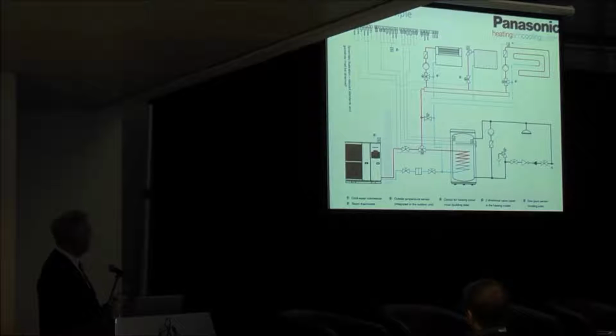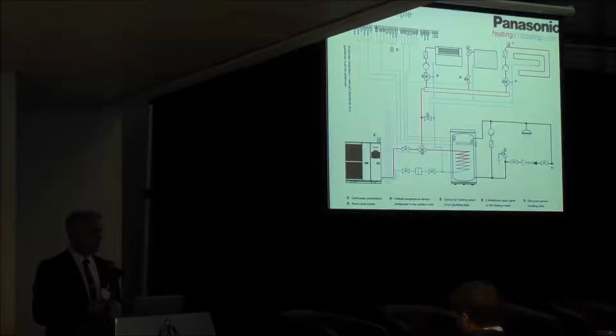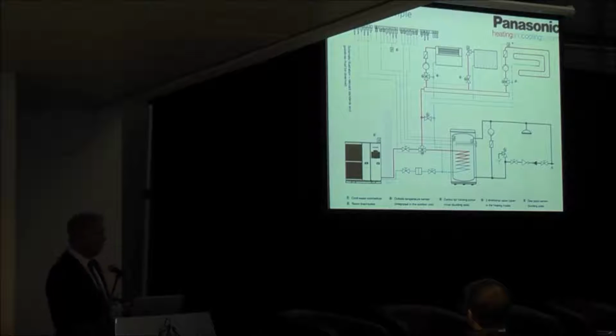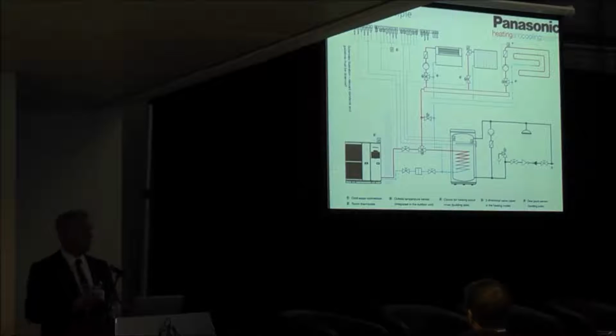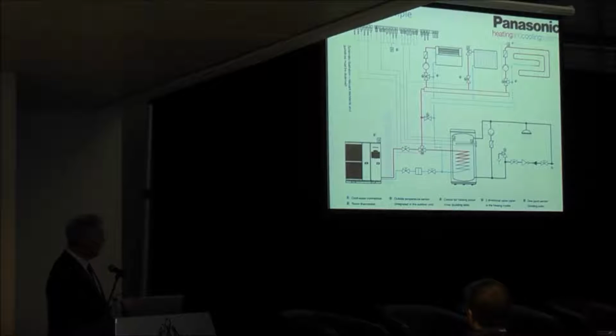Okay, friends. We size the heat pump for the biggest load, be it the heating in the house or the hot water. In a passive house, the biggest load is probably going to be your hot water demand. But the heat pump is sized to do your biggest load, one or the other. It's not sized for both. So we have a flow and return coming into the house. We're feeding the domestic hot water cylinder first. So when we commission the heat pump, the first thing we do is charge the hot water cylinder.